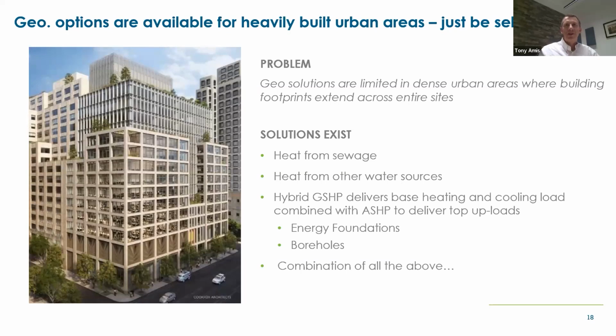And then there's the hybrid ground source heat pump solution. I call it hybrid because the picture on the left there you see is a commercial building. It had 63 foundations in it, 120 feet each. When we did a quick calculation, we couldn't deliver all the heating and cooling to that building from those foundations. So there are options, and the options are that we can add geothermal boreholes in amongst those foundations if necessary, or we can look at an air source heat pump that helps to deliver that peak cooling situation for the winter and summer time scenarios.